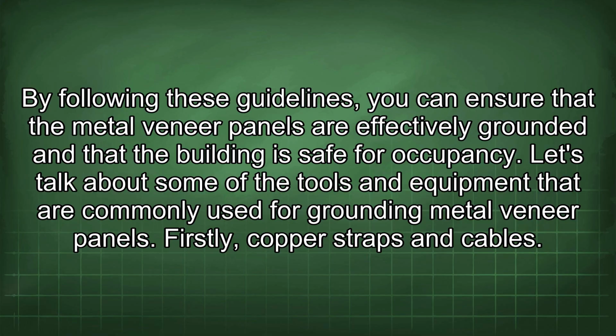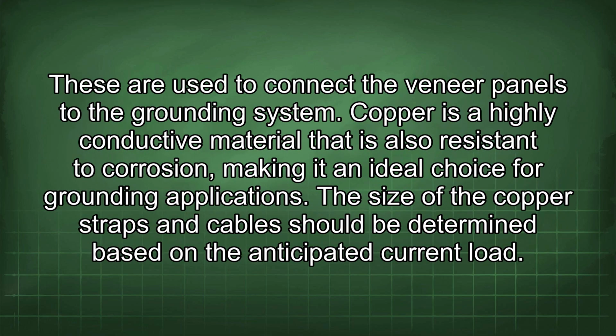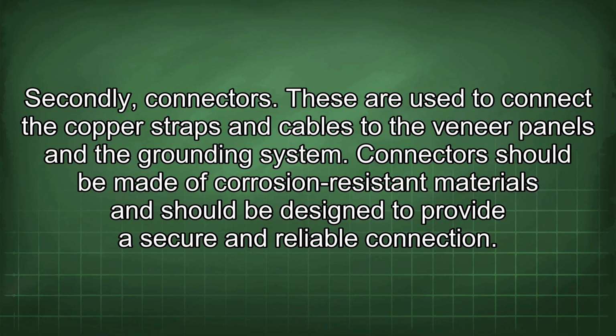Let's talk about some of the tools and equipment that are commonly used for grounding metal veneer panels. Firstly, copper straps and cables. These are used to connect the veneer panels to the grounding system. Copper is a highly conductive material that is also resistant to corrosion, making it an ideal choice for grounding applications. The size of the copper straps and cable should be determined based on the anticipated current load. Secondly, connectors. These are used to connect the copper straps and cables to the veneer panels and the grounding system. Connectors should be made of corrosion-resistant materials and should be designed to provide a secure and reliable connection.